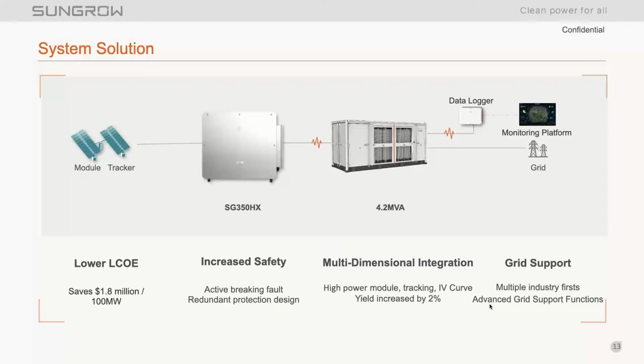And increasing safety, not only for operators, but for technicians and O&M personnel, as well as safety of equipment and land. Land and project square footage is becoming more and more precious. So we want to make sure that we're being good stewards of the square footage that we're taking up out in the field. So by improving safety, we're investing in the confidence that's being given to Sungrow. So the active braking fault is a redundant protection design that we have built into the DC switch there. So safety is definitely at the forefront of the design.